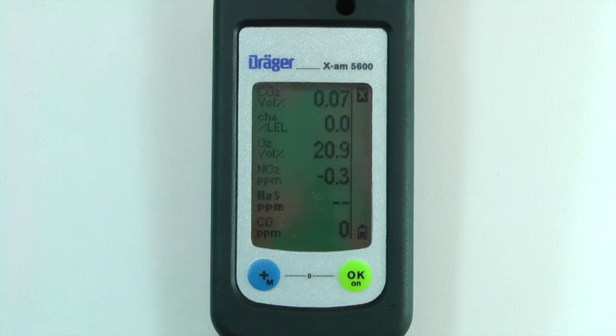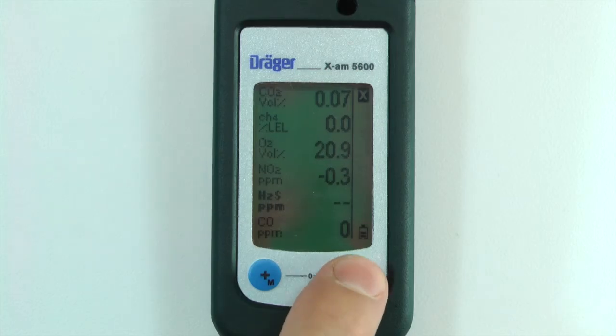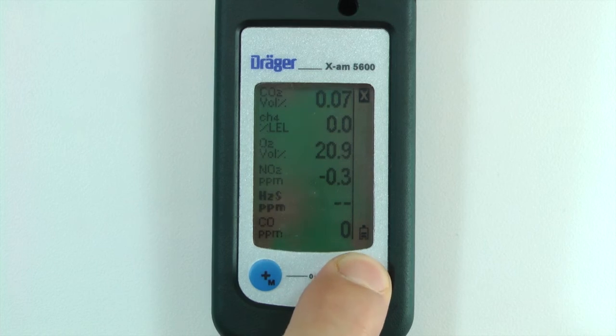The Info Mode displays more information about warnings, errors, peak values, and both TWA and STEL values. To enter Info Mode, press the OK key for 3 seconds.